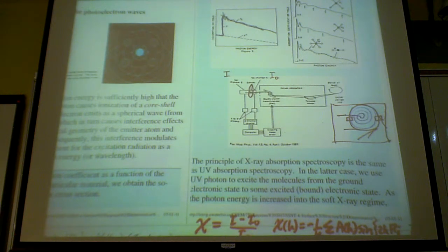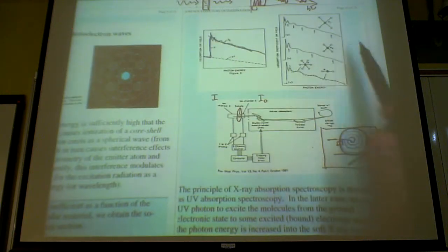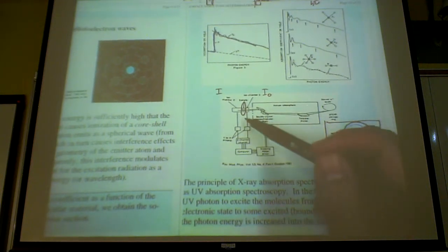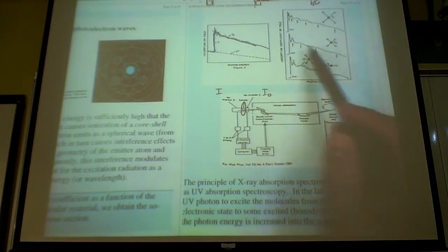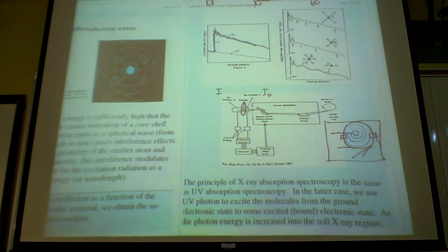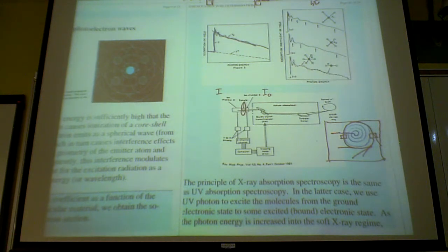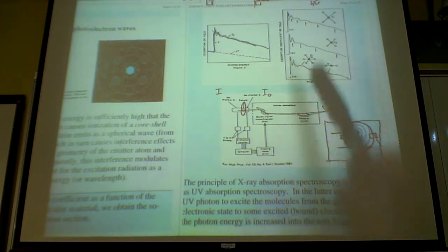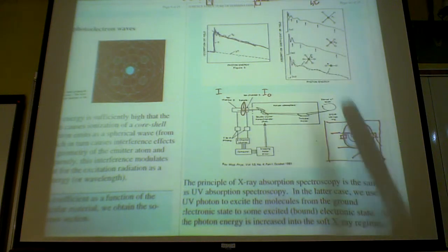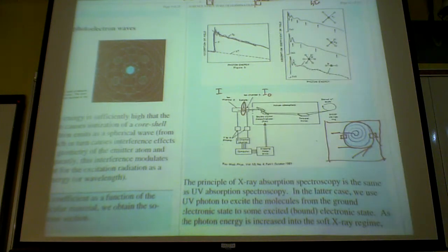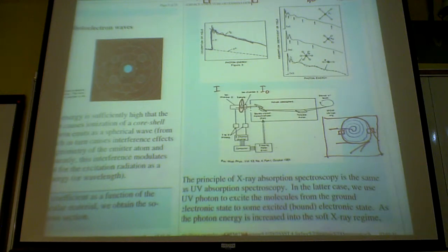But the problem, of course, as I alluded to earlier in XAFS, is that your measurement has to be so good. Remember, these little wiggles are under 5%. You cannot have a lot of noise in your measurement. And these experiments usually extend over a period of 2 to 5 hours. Literally, you have to make sure that your measurement is stable over that time, down to 5%, which is not so easy to do. So sensitive electronics is what you need.